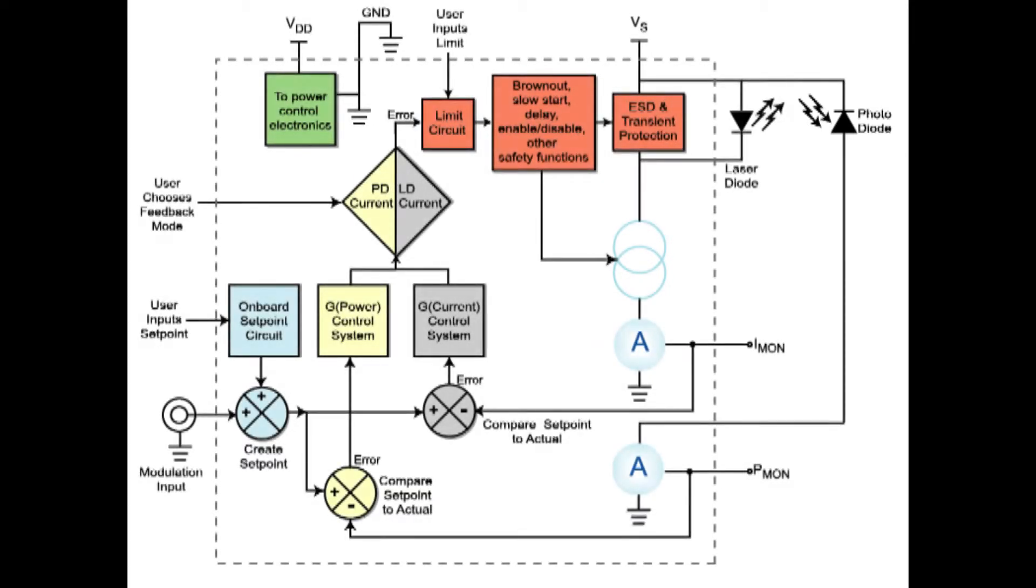Current is measured through the laser diode or photodiode and translated into a voltage. Imon represents the current through the laser diode. Pmon represents the current through the photodiode.